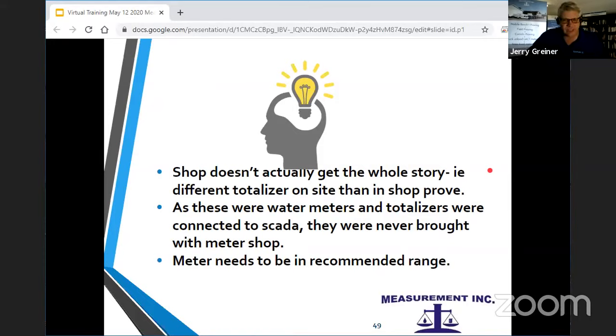They're water meters and the totalizers connected to SCADA, so the totalizers were never brought with the meters when they come into the shop. The meter does need to be in the recommended range, which they were, but because the totalizers wouldn't count at the bottom, it didn't actually work. So that's what we learned about our totalizers.